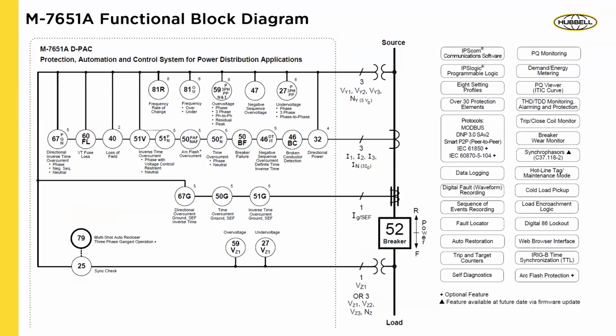When we look at the functional block diagram, you can see that we have a breaker, and the power is reverse on the top and forward at the bottom towards the load. We have 3-phase CTs that get attached to the relay, and then you have 2 voltage sources, one on the source side, one on the load side, and then several of the elements that are voltage elements. And on the right side, you'll see all the other applications that typically come with this M7651A DPAC. A lot of them are standard, and others are more optional.